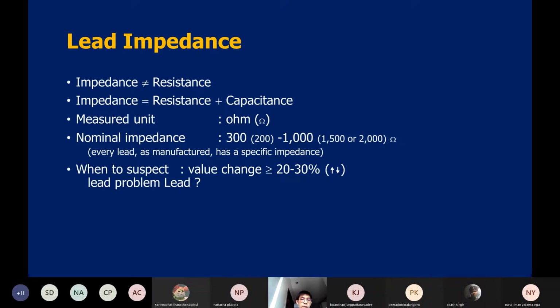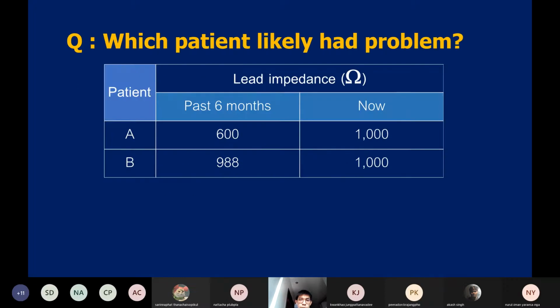The unit of impedance is the ohm, and the nominal impedance is around 300 to 1000. It depends on the manufacturer. With different manufacturers, sometimes the normal impedance is around 200 to 2000. The important thing is that you follow up the impedance and see how different the current impedance is from the previous check. So, do you know which patient is likely to have a problem with the leads according to the impedance? Patient A or B?